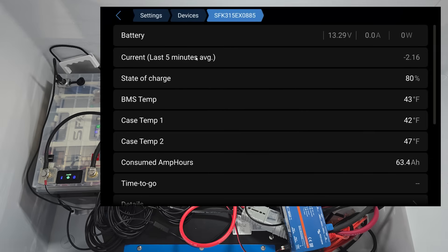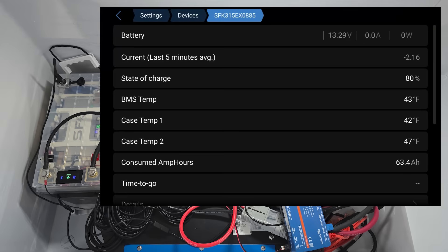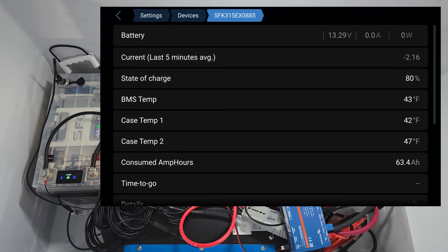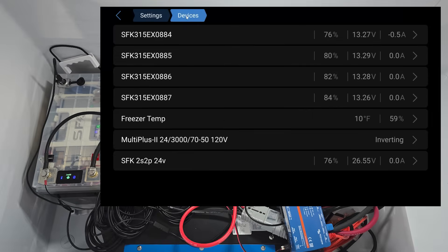All right. And if we look at maybe another battery, you can see this one's 42, 47. So already you are seeing not all batteries are going to be around the same temperature. Some might be closer to a gust or wind, a wind source. So they might be cooler and others will be slightly warmer. So that's why we have the synchronized heating as a range because the batteries are going to be exposed to different ranges. And this is a more realistic thing is consume the power that you need to keep them warm, but don't necessarily only heat one and not the other. And then you end up with an imbalance where it's going to take longer to balance out. And yeah, by doing this way, you have that flexibility of running them all.